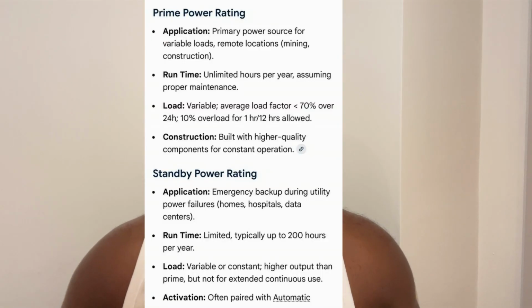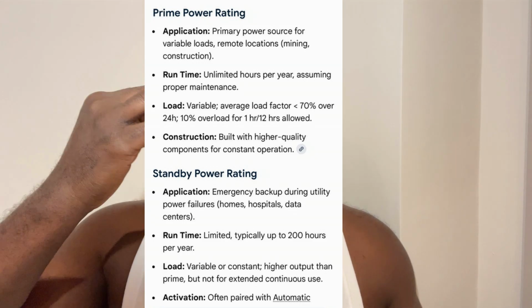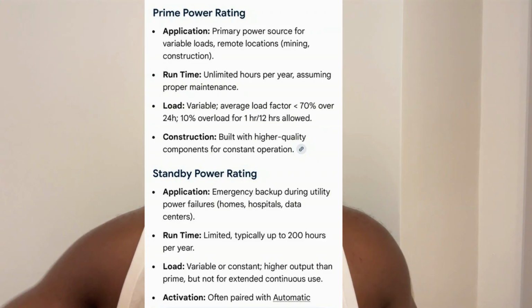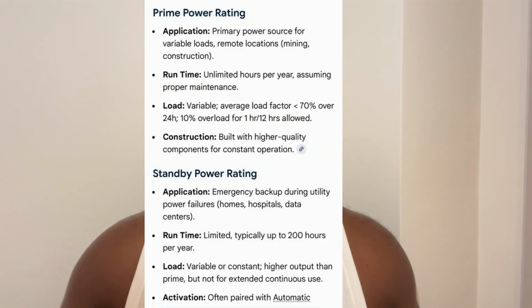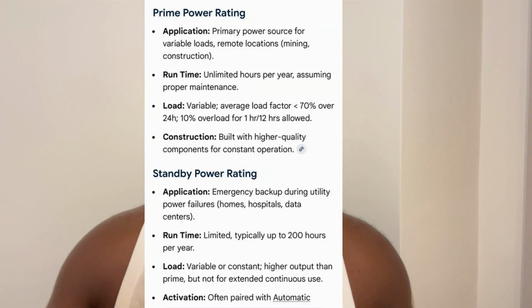Let's talk about the brand and the engineering differences. There's something called standby generator rating and prime power rating. Some generators are designed for 24/7 prime power rating or continuous duty rating, whereas some are called standby ratings or emergency power ratings that are designed for shorter durations in the year, and have less durable components.